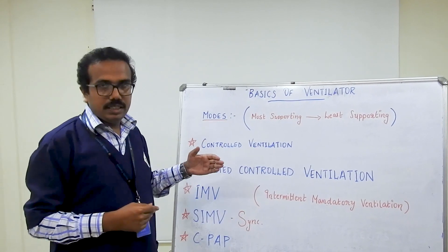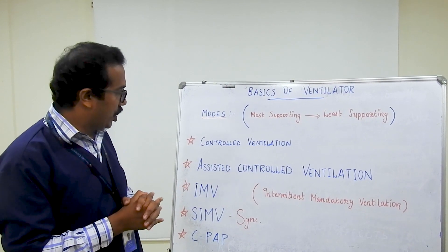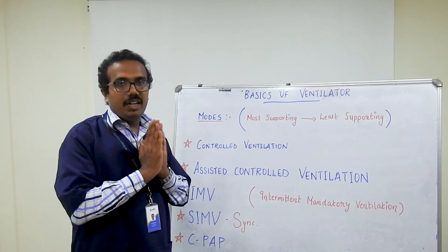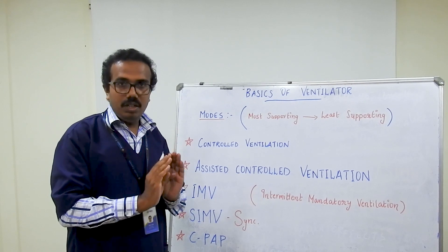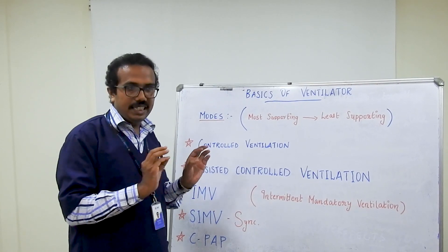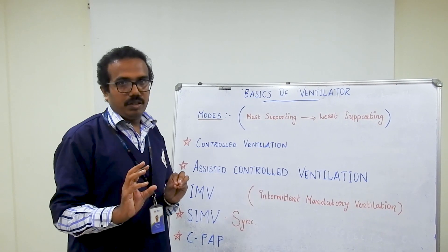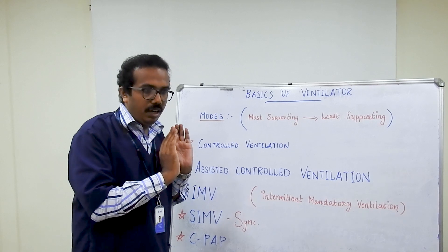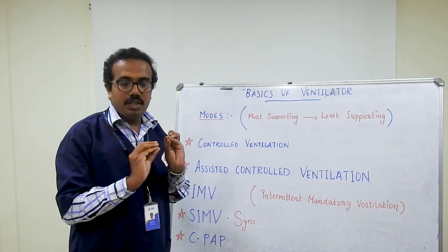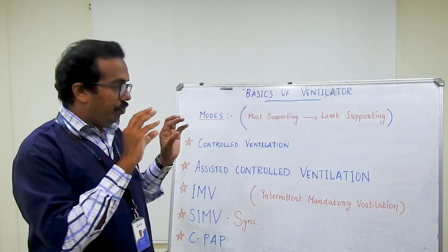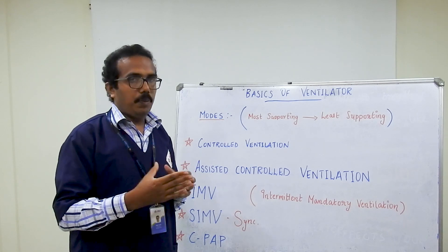First, we discuss the most supporting mode — controlled ventilation. In controlled ventilation, the ventilator is fully in control. We can set the tidal volume or respiratory rate. When the set tidal volume or respiratory rate is delivered, the ventilator delivers the breath. However, if the patient attempts spontaneous breathing, the ventilator will not support those spontaneous breaths.